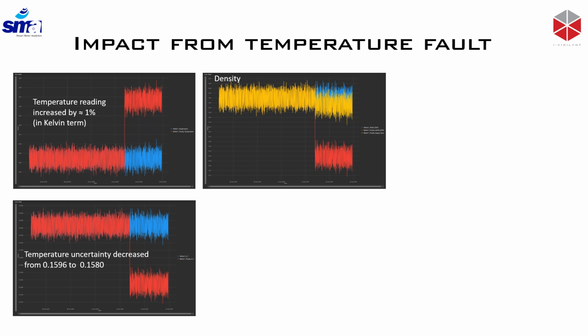The impact on the density is quite interesting, because if you see in that particular box, the correct density compared against the kappa density has only a 0.16% discrepancy. So the kappa density went down by 0.16%. The AGA density, however, went down by 1.4%.